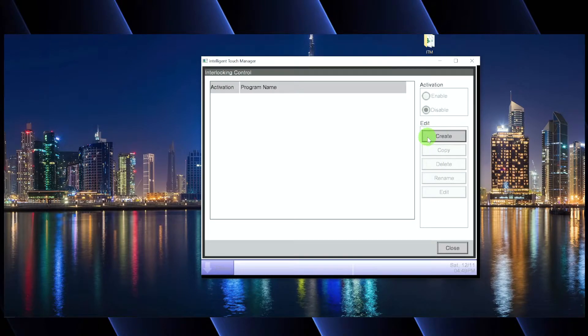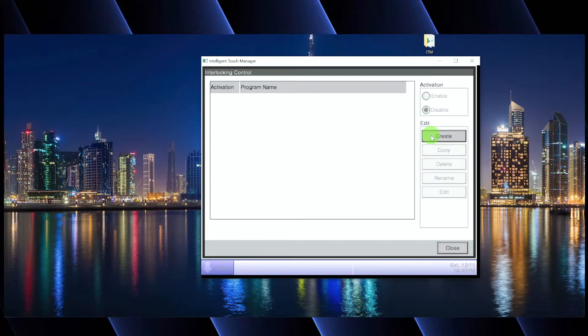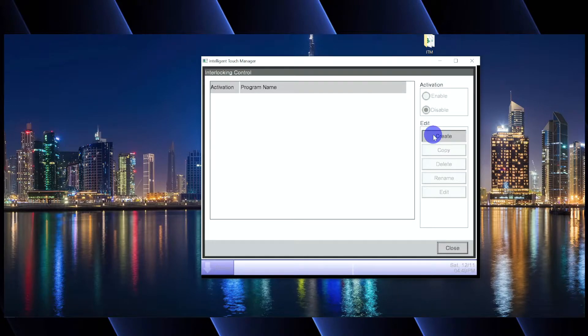Back on our ITM, from the main screen to get to the interlock menu setup, click the menu button at the bottom and then click on interlocking control. We're going to create a new interlock. We're going to create one where the humidity and temperature analog inputs from our WAGO get above a certain amount, and we're going to have an indoor unit on the Daikin VRV system switch modes to cooling.